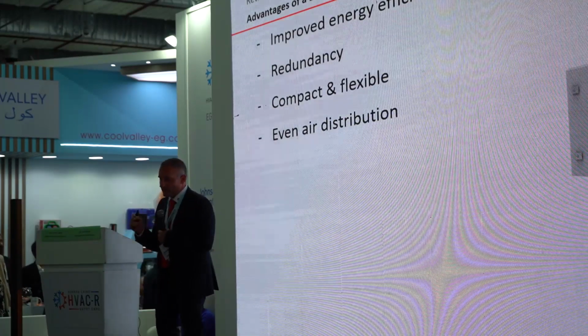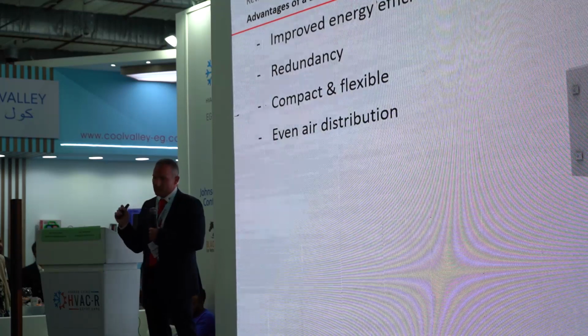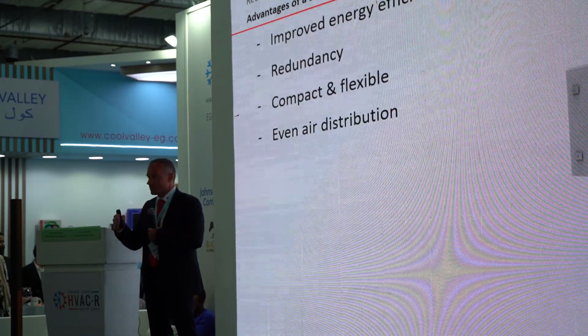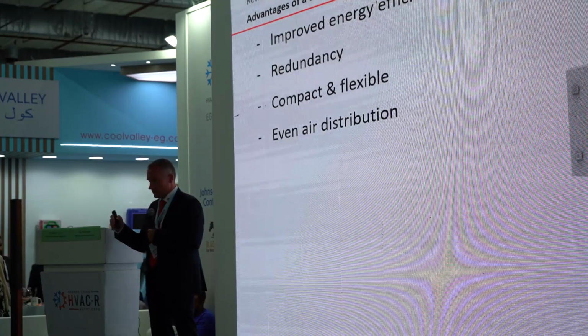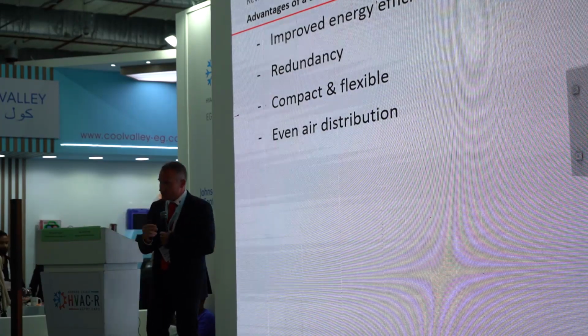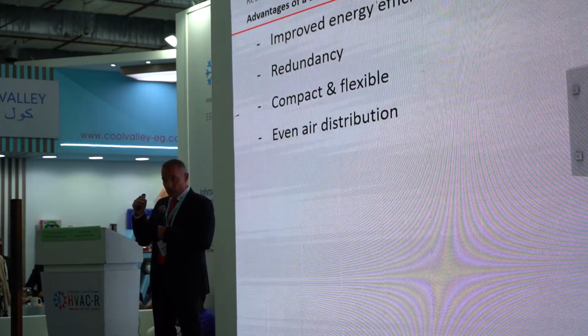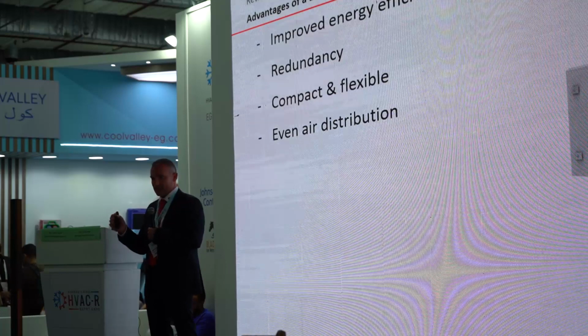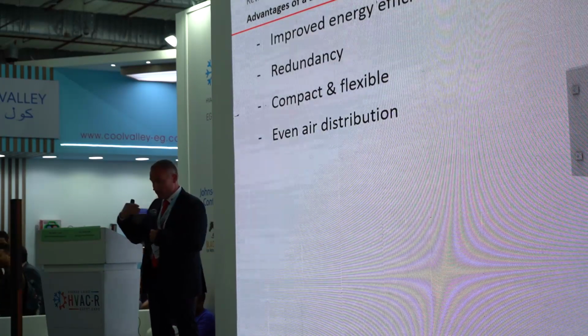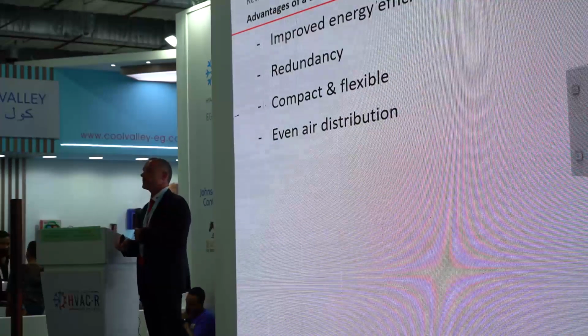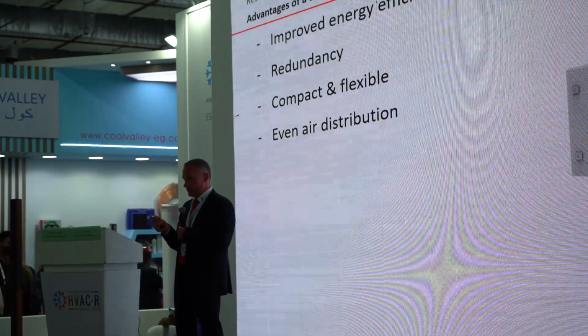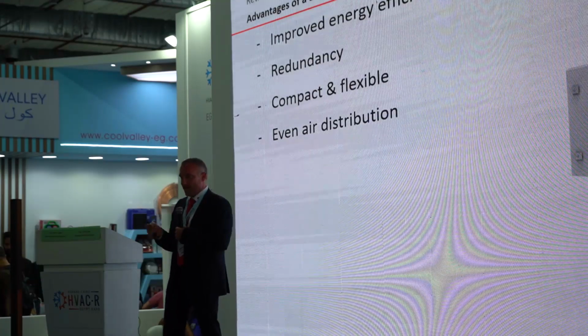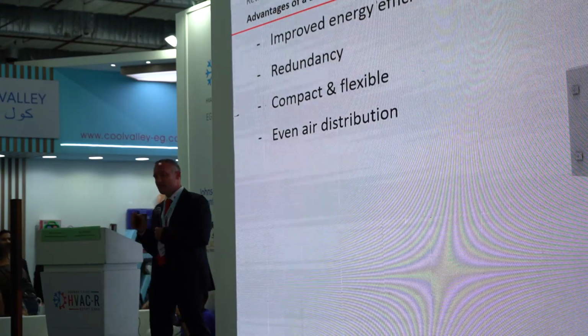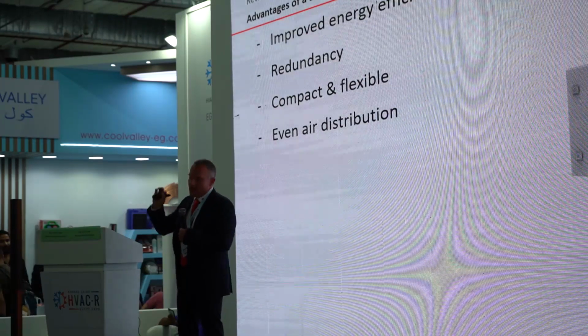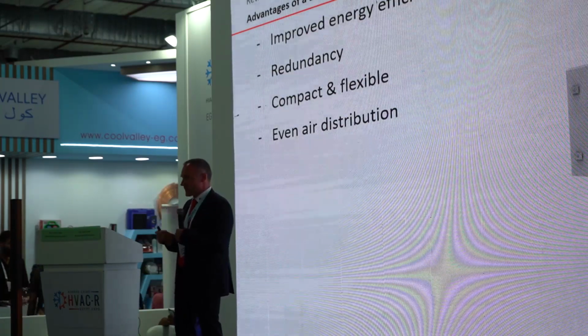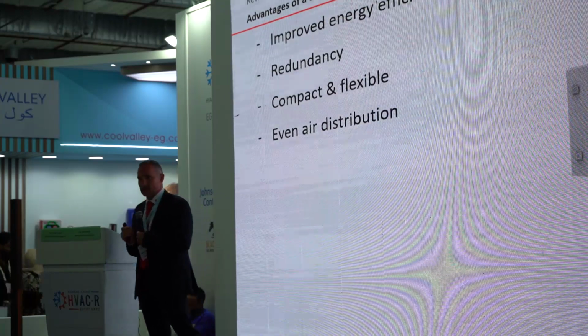And there's another point. On all the belt-driven fans, you see this diffuser on the pressure side to make the airflow equal. It's a plate with holes. With the EC fan grid you can get rid of this plate, and that means you can reduce the needed pressure. This plate often creates a loss of 70, 80, maybe 100 Pascal of pressure. What is the message here? If you reduce the pressure, you reduce the energy consumption.